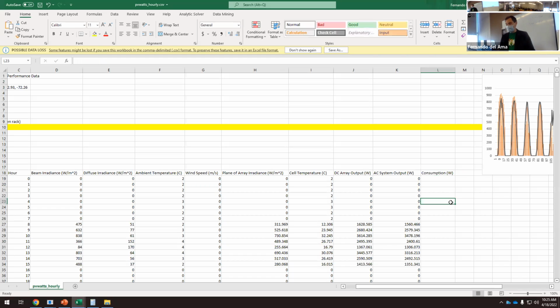But now that requires a lot of effort because we need to understand the actual consumption of this building. If we are talking about this classroom, if we have 16 computers here or 18 computers, the computers are not working. They are on saving mode. What's the consumption of computers on saving mode? 20 watts. 20 watts times 18 or 20 would be 400 watts.